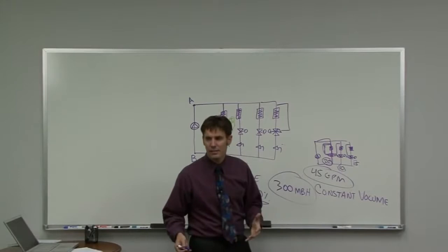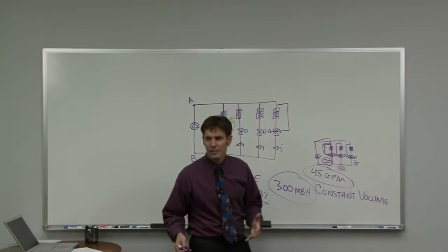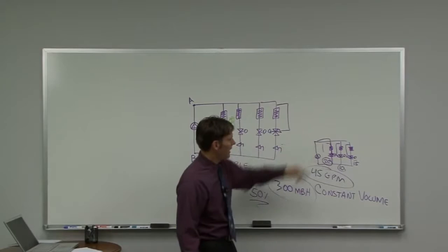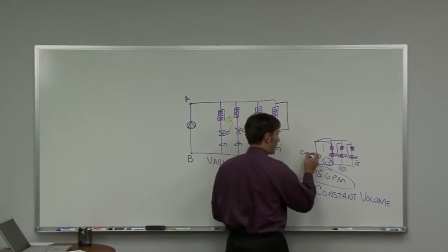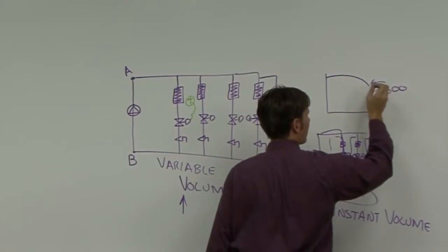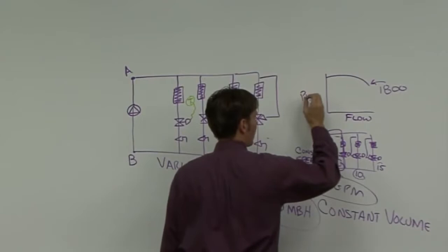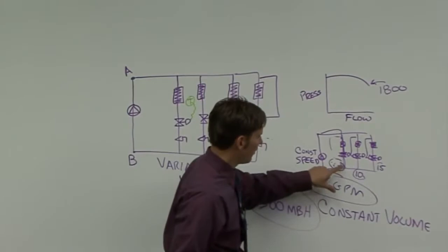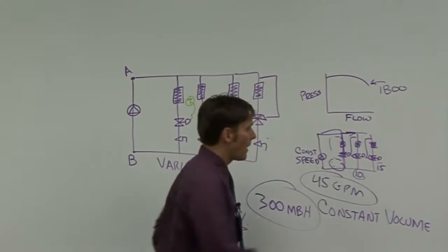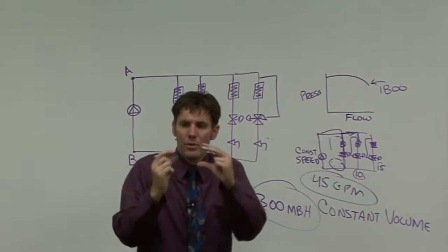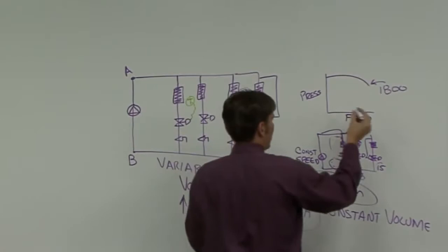Does it even make sense to flow water to circuits that don't need it? We're wasting energy. Why flow 20 GPM through a circuit if we don't need it? Close it off, put it in a two-way valve system. With a constant speed pump operating at 1800 RPM, when a valve closes and I no longer flow 20 GPM through that circuit, I try to squeeze that same flow through the remaining pipes. The pipe diameter didn't change — so as I squeeze more water through the same diameter, pressure goes up and my flow rate decreases.